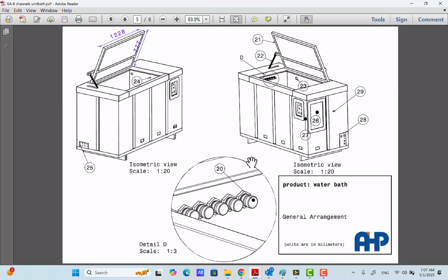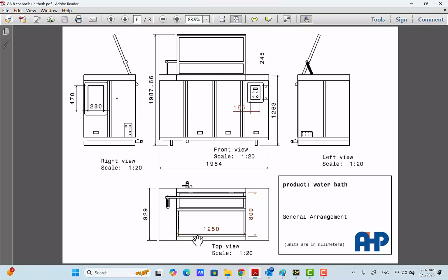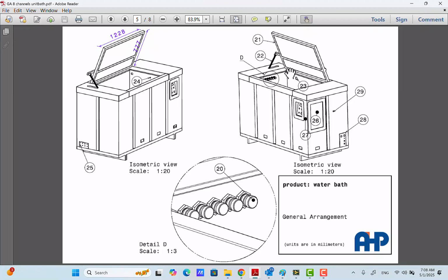The water is collected from a collector inside the bath. The collector here, let me see in which picture you can see it. If you take a look inside the bath, you will see a douche here, in the top corner side. And right in front of that douche, you will have a collector to collect the water inside the tank and bring it to the small tank inside here on the right side with the heating element inside it. And on the top side of the small bath, there is a circulation pump that brings the water, passes the water through the heating element, brings it to the douche, and circulates the water for the temperature homogeneity inside the tank.